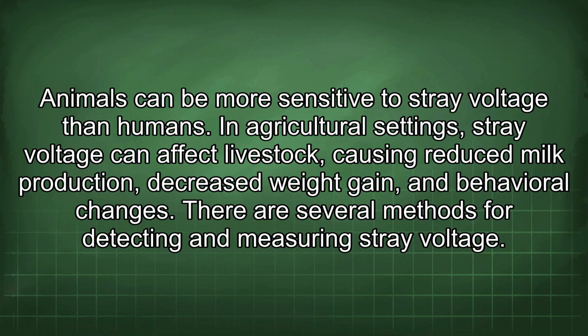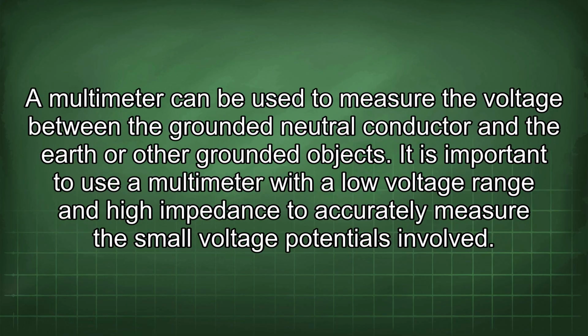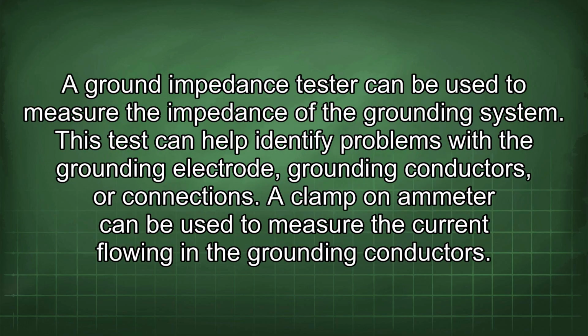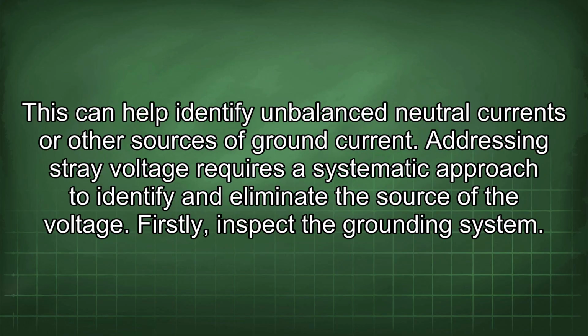There are several methods for detecting and measuring stray voltage. A multimeter can be used to measure the voltage between the grounded neutral conductor and the earth or other grounded objects. It is important to use a multimeter with a low voltage range and high impedance to accurately measure the small voltage potentials involved. A ground impedance tester can be used to measure the impedance of the grounding system. This test can help identify problems with the grounding electrode, grounding conductors, or connections. A clamp-on ammeter can be used to measure the current flowing in the grounding conductors. This can help identify imbalanced neutral currents or other sources of ground current.